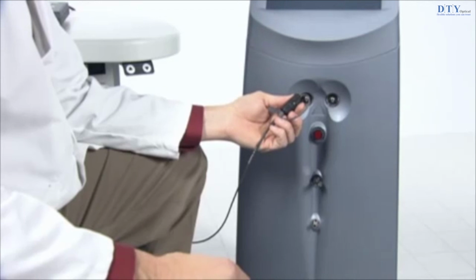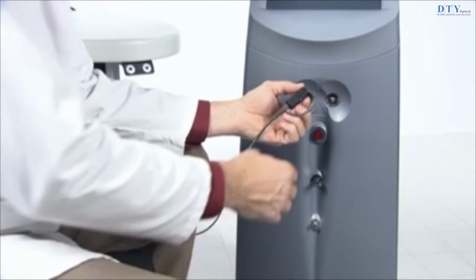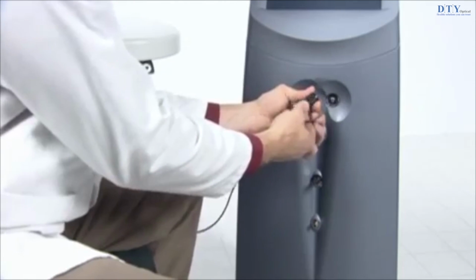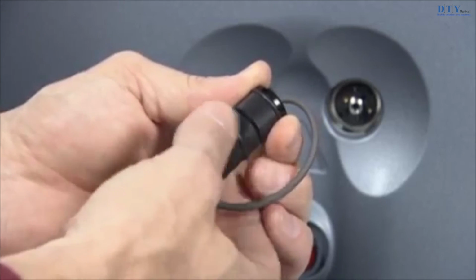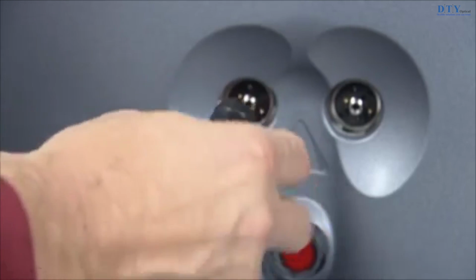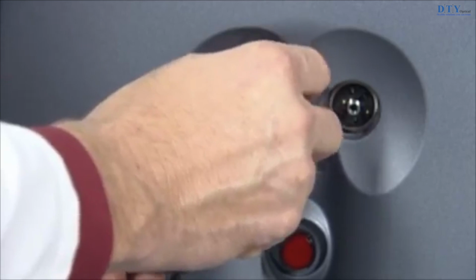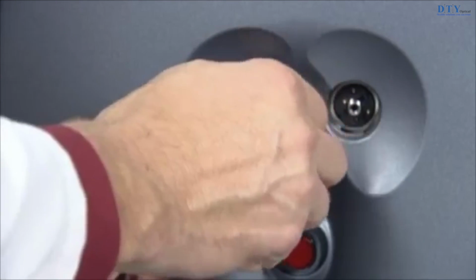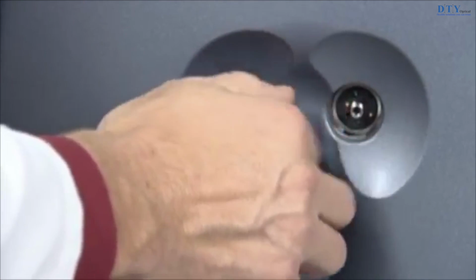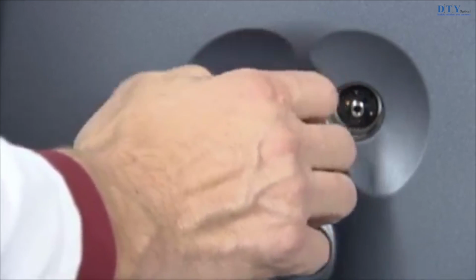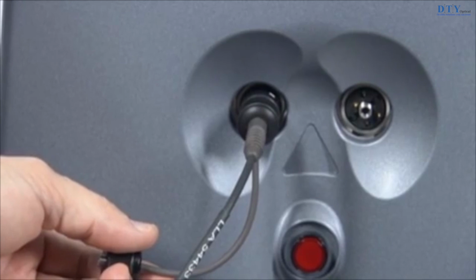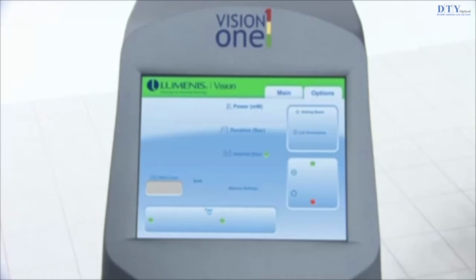To connect a delivery device, attach the delivery device laser connector to either fiber receptacle on the front of the laser console. If using a compatible laser indirect ophthalmoscope, you may also connect the LIO illumination power receptacle on the front of the laser console. Refer to the appropriate delivery device operator manual for the detailed instructions of the use of the delivery device.